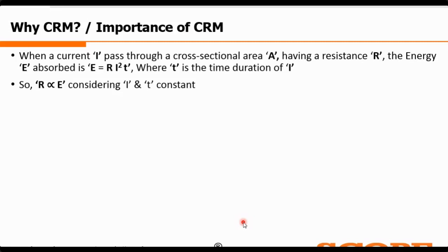Now, because of the heating effect, two things may happen. One is that the carbon deposition will start to form in the contacts. When the carbon deposition forms, the effective resistance of the contact increases. So when the rated current is continuously flowing, because of the cascading heating effect, the I square R loss continuously increases.